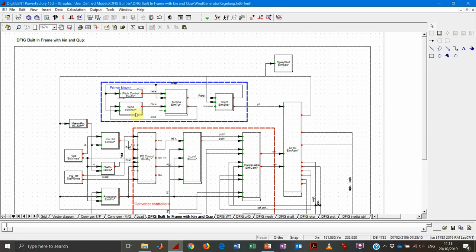Within the prime mover area we have four blocks. The first characterizes the wind — the equivalent wind speed seen by the wind turbine. Then the dynamics of the pitch control system. Then the turbine — the aerodynamic characteristics of the wind turbine. And the dynamics of the shaft, meaning the masses of the high-speed and low-speed shafts, and the flexibility or stiffness of the gearbox. Out of these blocks we get the power that is sent to the DFIG generator.